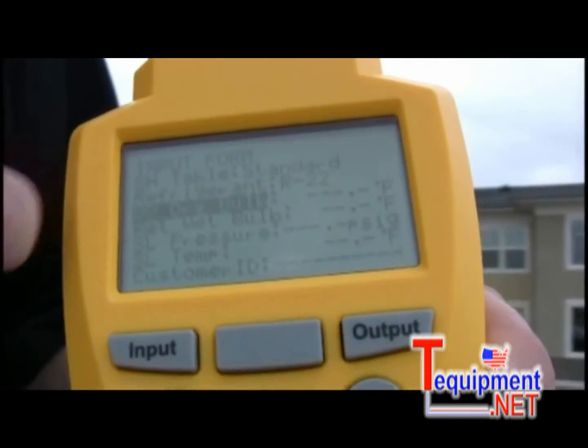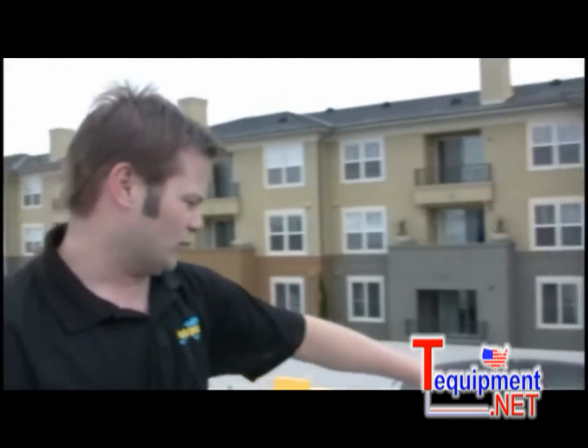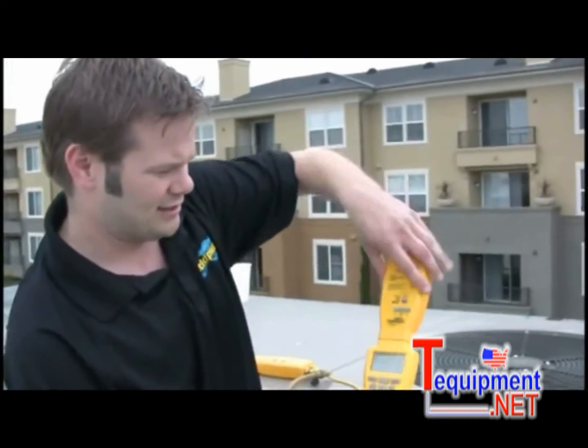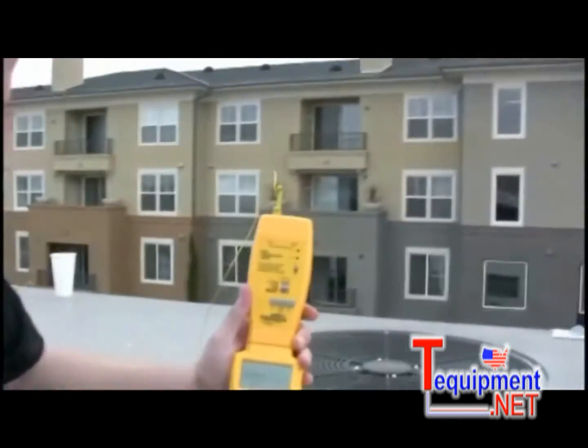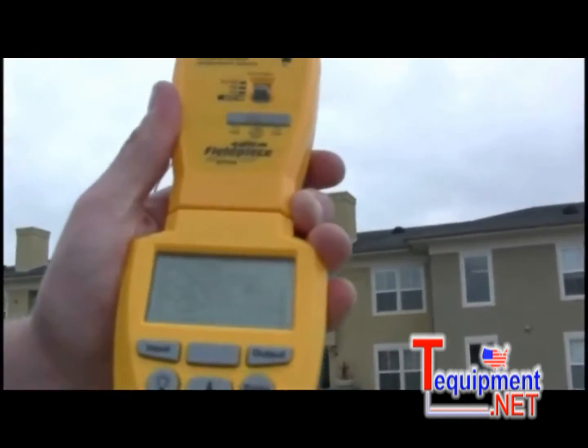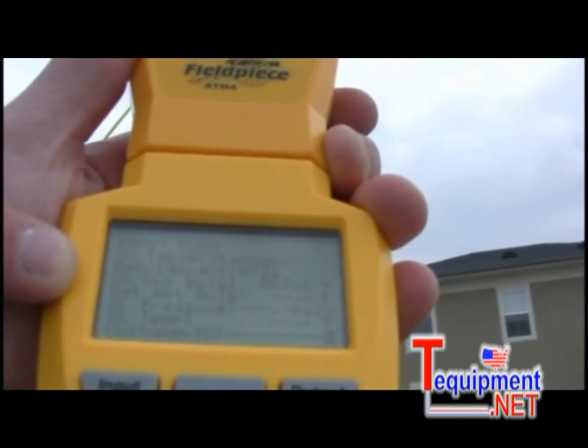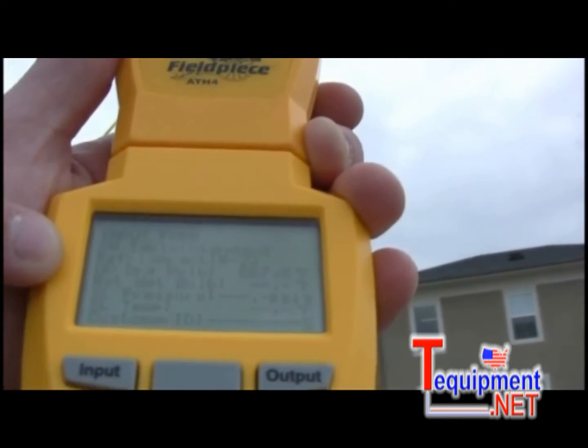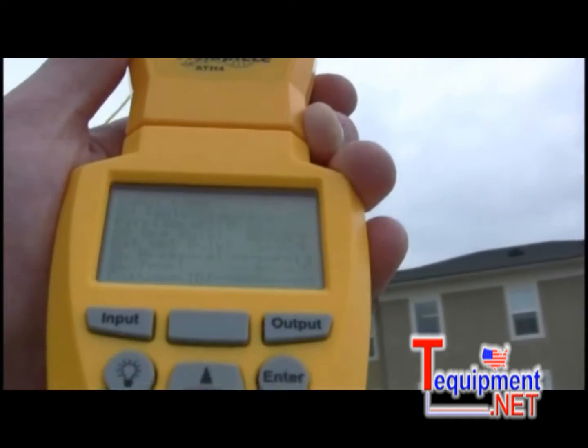Now the next thing on the test is the outdoor dry bulb. So I'm going to go over to my dual temperature head, attach that to the HVAC Guide, and turn it on. Then I'm going to press enter to start taking that measurement, and you can see that it puts a 67 degree temperature for my outdoor dry bulb. That's pretty stable, so I'm going to press enter to lock it in.